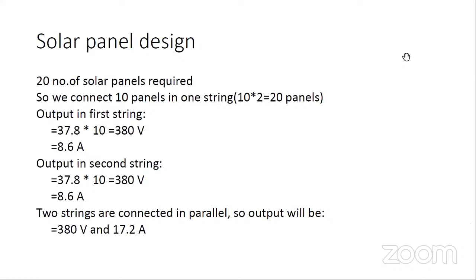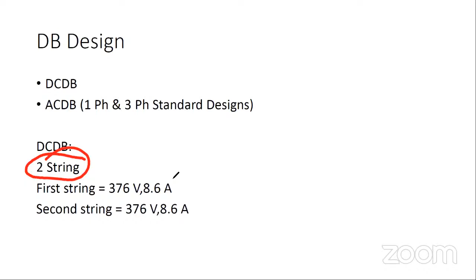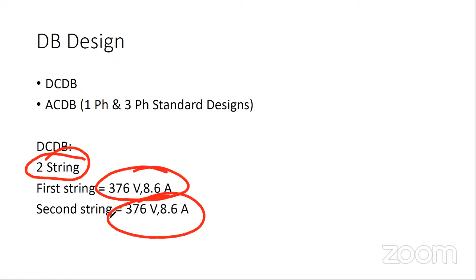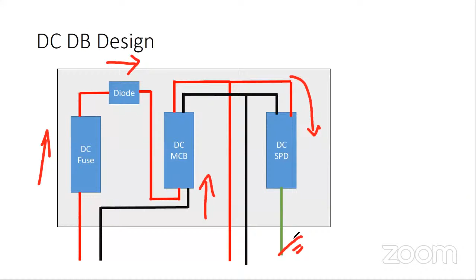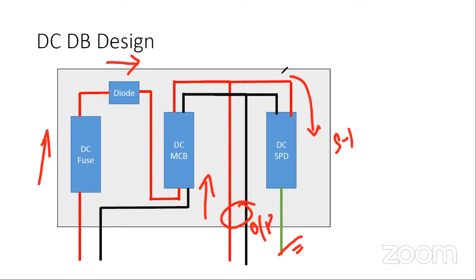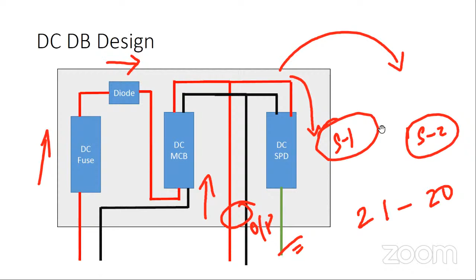Now the PV module strings are going to be connected to the inverter. That is our inverter. Before the inverter, the DB box comes into place. So here, how many strings are required? Two strings are there. The first string is 376 volt, 8.6 amps. The second string is the same. Now, this is the DC-DB box. As you already saw in the component section, the first line of protection is the DC fuse, second is the diode, then it comes to the DC MCB, and finally it goes to the SPD. This is going to the earth, and this is the output. This is for the first string. Similarly, the same mirror image is replicated for the second string in the same box. So this is nothing but a 2 in, 2 out box for this particular design.